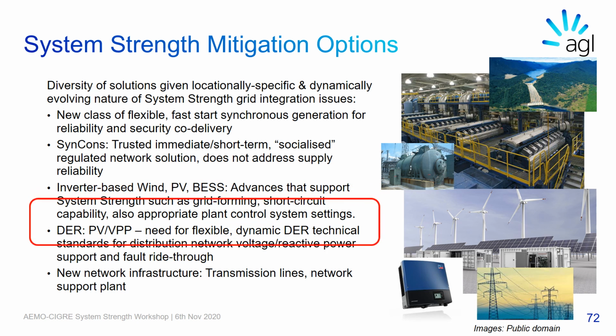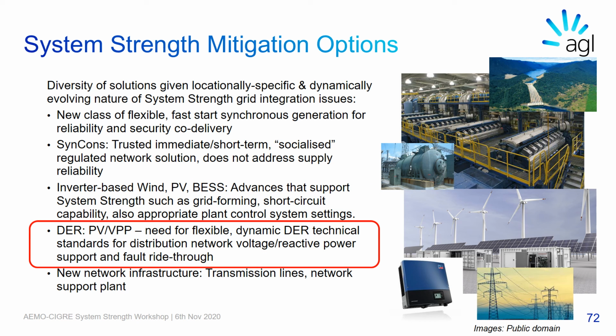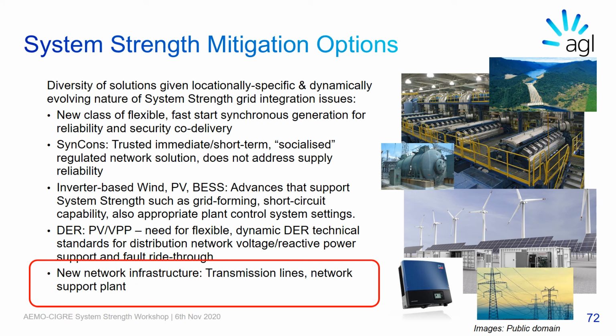Now, as for DERs, in particular distributed PV and virtual power plants, they have a supporting contribution to the overall network system strength issue by ensuring that embedded generation has sufficient capability to ride through voltage faults and to not exacerbate primary dynamic stability issues on the transmission network. This points to the need for flexible dynamic DER technical standards, in particular those relating to medium voltage and low voltage network voltage management and dynamic fault ride-through network support. Lastly, new network infrastructure is part of the overall Swiss Army knife, in particular to reduce network electrical impedance and also to provide N-1 coverage of any planned or unplanned outage of critical transmission assets.